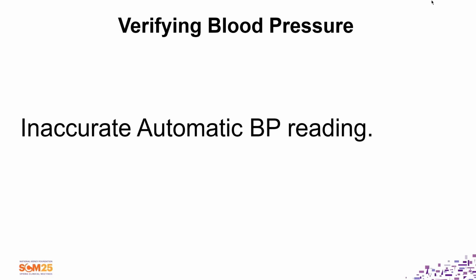That pressure monitor, that transducer is very, very accurate. And it's going to give you the correct pressure reading. It might not give you the correct blood pressure, but that reading is correct. So you use that as your gauge while you're listening. And then what you hear in relation to that pressure is your blood pressure accurately. Unless you're deaf. Right? So for an inaccurate auto reading, don't keep asking, do you know where the manual blood pressure cuff is? You have one on your machine.